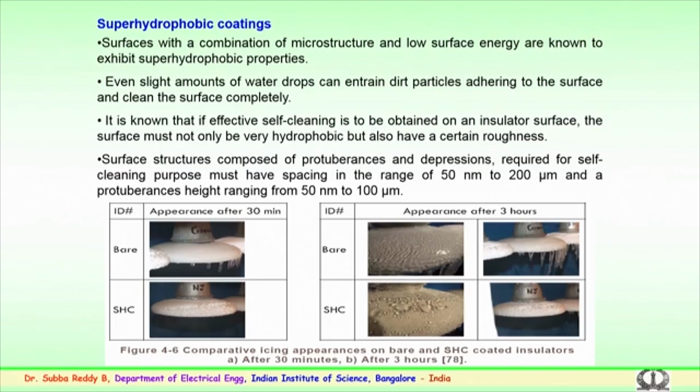So, here you see the comparative icing appearances on bare and super hydrophobic coated insulators for 30 minutes and also after 3 hours. This is a bare insulator, and this is a super hydrophobic coated insulator for 30 minutes. Here you can see the appearance after 3 hours. So, these coatings do help in better performance in the field.